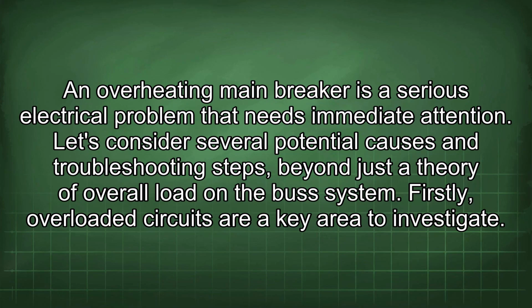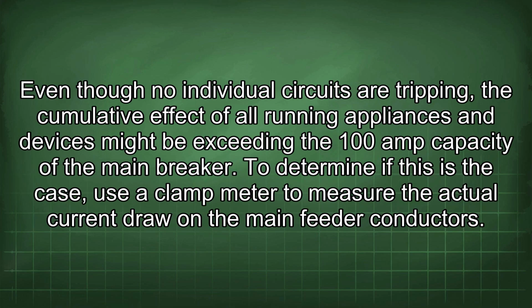An overheating main breaker is a serious electrical problem that needs immediate attention. Let's consider several potential causes and troubleshooting steps beyond just a theory of overall load on the bus system. Firstly, overloaded circuits are a key area to investigate. Even though no individual circuits are tripping, the cumulative effect of all running appliances and devices might be exceeding the 100 amp capacity of the main breaker.